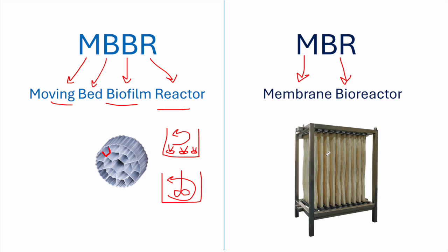We have pre-screening to highly reduce total suspended solids. We also place the wastewater in anoxic and aerobic conditions to highly reduce nitrogen, COD, and BOD. Finally, the membrane bioreactor stage serves as a secondary stage, and this membrane is able to produce a highly treated wastewater effluent.